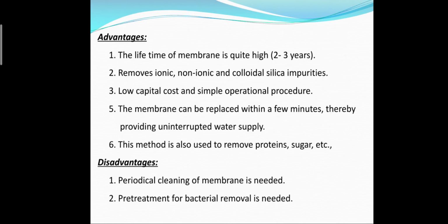Some of the advantages of reverse osmosis are the lifespan of the membrane used in this process lasts for 2 to 3 years. Ionic, non-ionic and colloidal silica impurities can be removed using this method. For this process, operational procedure is simple and capital cost is quite low. Replacing the membrane takes few minutes so that it assures uninterrupted water supply. We can also remove protein and sugar by using this process.